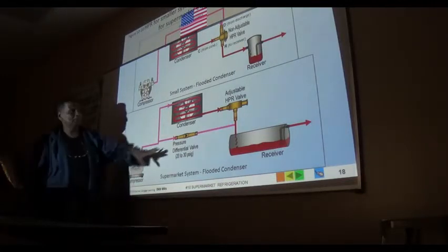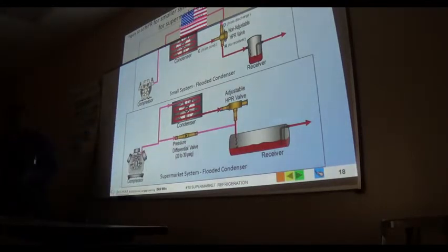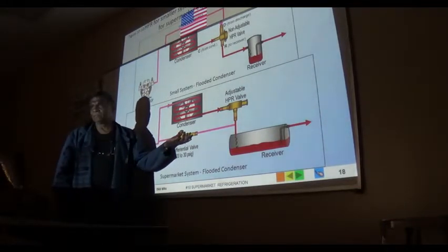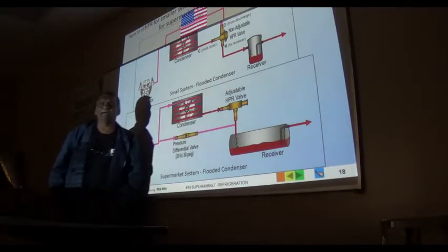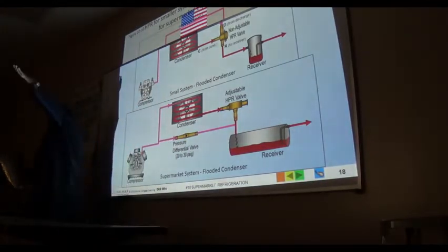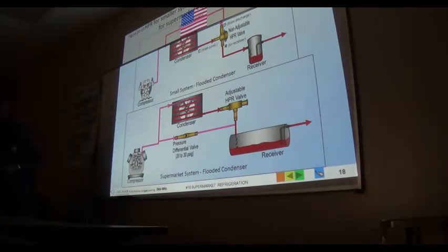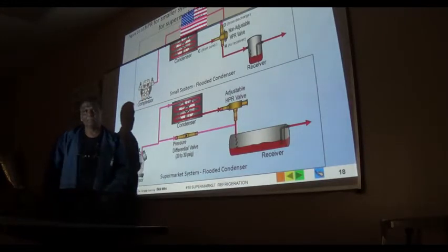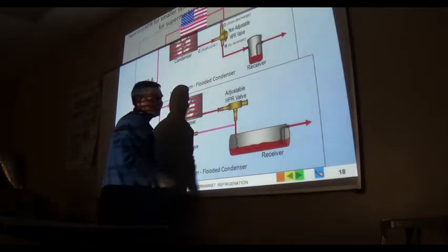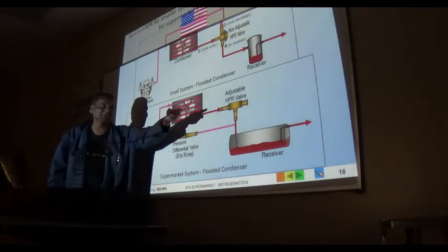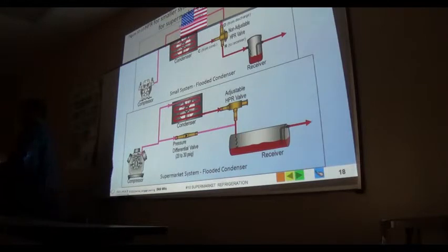But this one, like I said, if you suspect one of them is bad, two things can happen. During the summer, you may find that this valve is not opening as it should. Head pressure will build up. Your compressor will cut out on high head pressure, always. All right, that's the one thing. It's going to work in the winter, but during the summer, that's the one problem with them. They kind of get stuck in one position. So if you check that and you find that's a problem, change this one too, because they work together. And if they were installed together, if that goes, chances are this one is going to be kind of funky. You have the system open, change it. They're cheap enough.